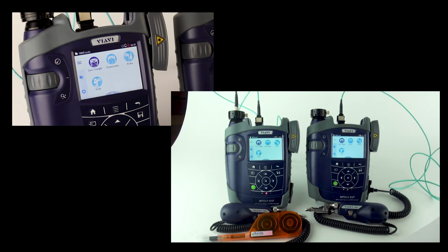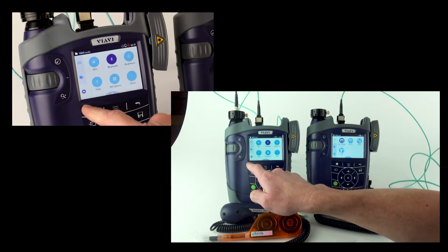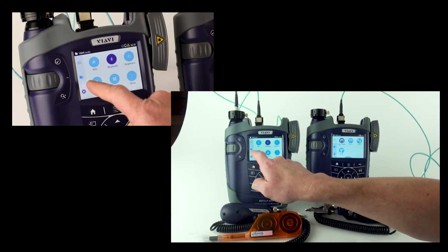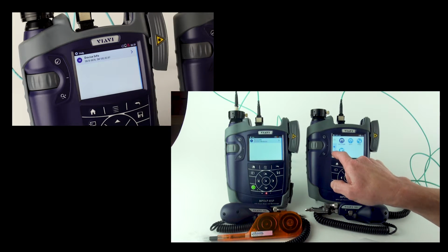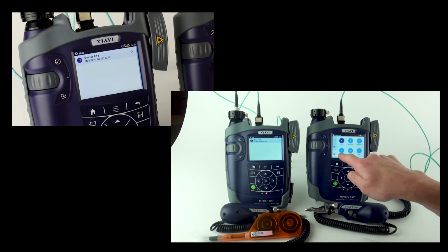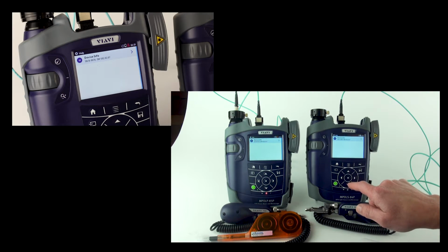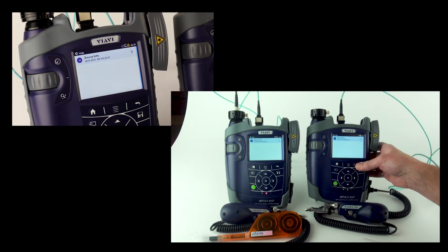You should review the user manual for the MPOLx and be very familiar with how to use it. One of the first things you have to do is make sure these units have the most current firmware installed. Go to scf.updatemyunit.net and download the latest firmware. If you want to see what firmware is on the unit, go under settings and press the help button. It tells you your power meter and your source must have the exact same software level, and in this case you can see that they do.